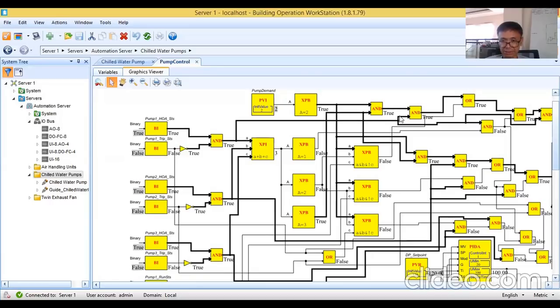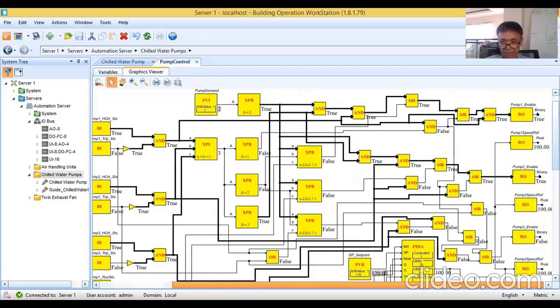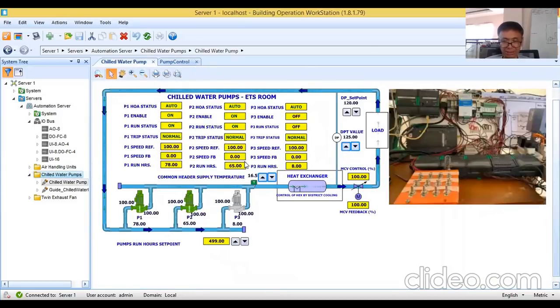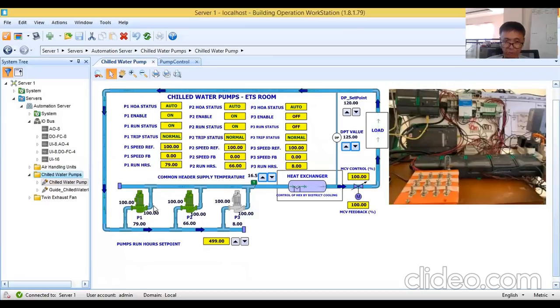There's a pump demand of two, so two pumps always run. The logic checks: if it's automatic and no trip, it flows through an OR gate. If there's only one pump available, separate logic handles that. As you can see, pump one enable is true and pump two enable is true. In the graphics, I have animations — when pump one is enabled, the flow animation shows water being delivered to the load.